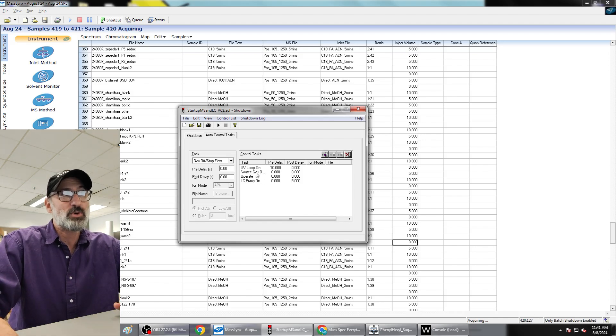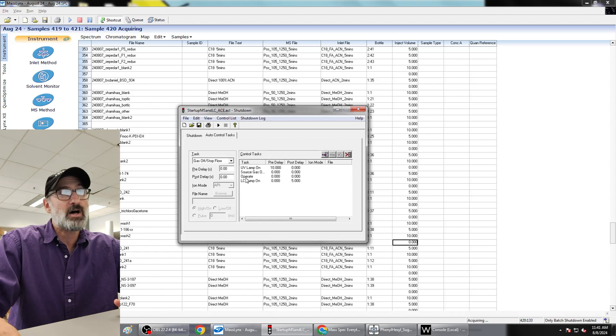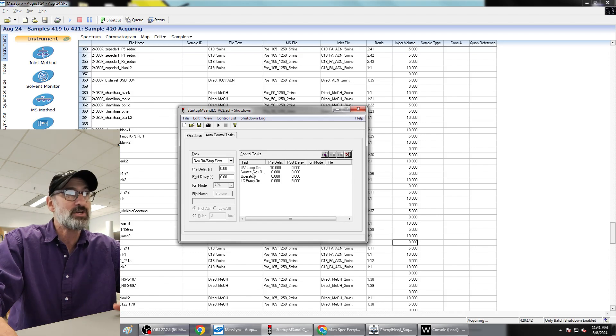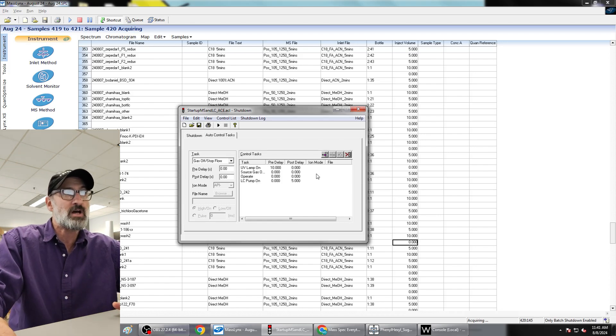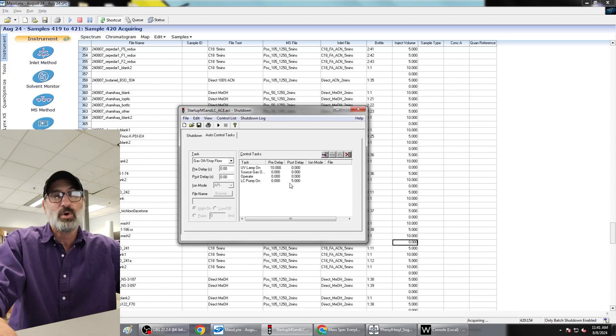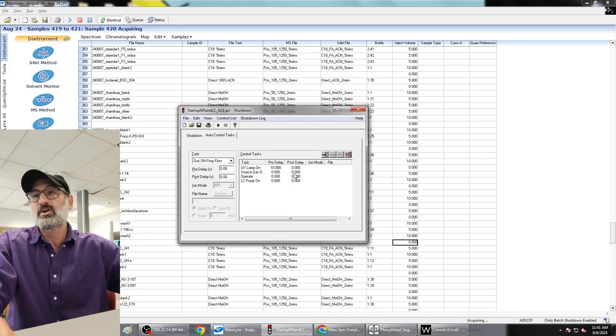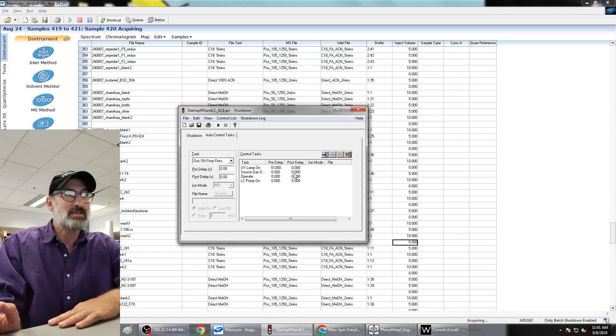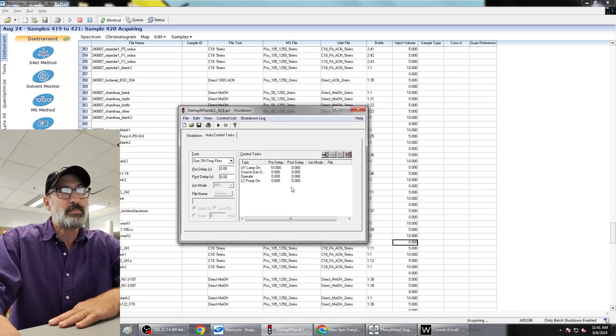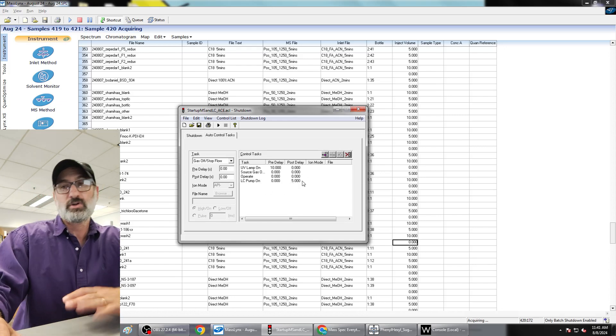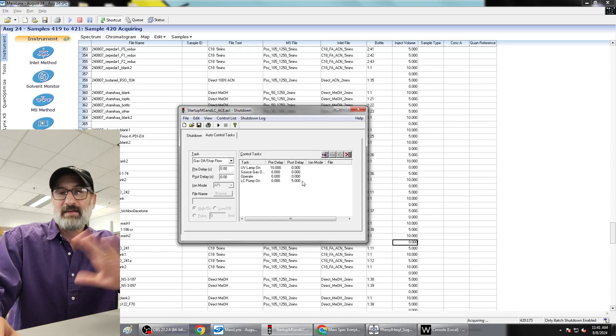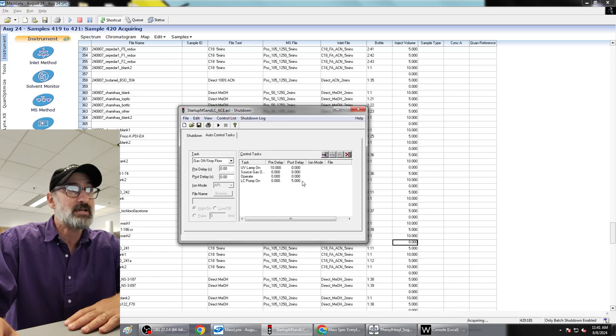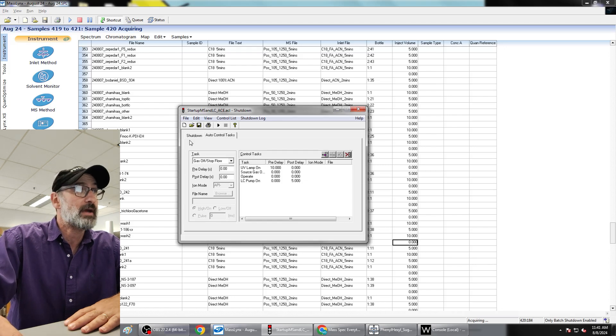Then at time zero I'm going to tell it to turn the source gas on. I'm also going to tell it to turn the instrument on as soon as it turns the source gas on, so they're both at time zero but it's going to do this in order. So it's going to do source gas on, then turn the instrument into operate. Then five seconds later, you don't want to do it too close, it's going to turn the pump on. So then the liquid is going to start flowing in the mass spec. And if you do it about five seconds later in the post delay, then you won't trigger that stop flow error. You've got to wait a little bit of time for the electronics to realize that it's got the gas on before you can turn the pump on.